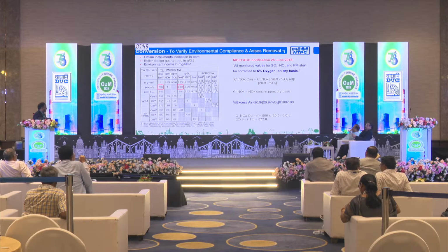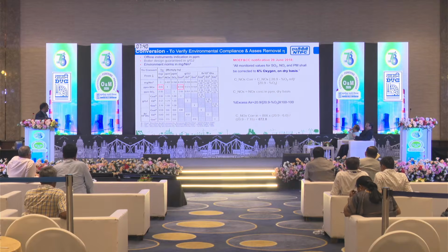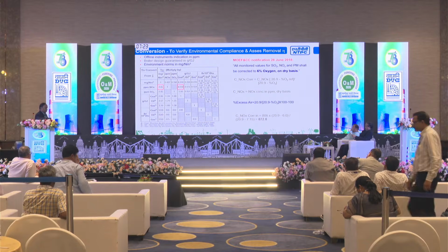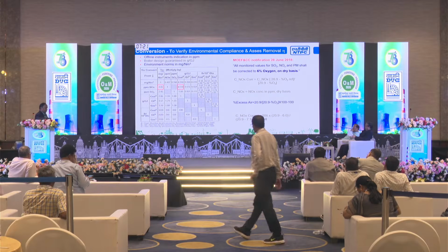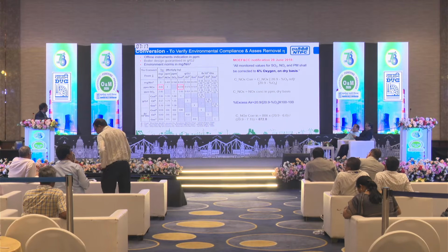So what is the reporting format for NOx? As per the ministry guidelines, we report all SOx and NOx in mg per NM3, corrected to 6% oxygen dry basis. These are the equations through which we can convert NOx into the required units or required value.